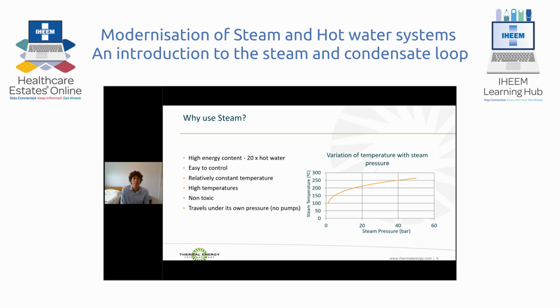So why do we use steam? I guess the key reason is the high energy content. It typically has 20 times more energy per kilogram than hot water. The reason for this is we're not taking the temperature energy out of the steam, we're using the latent energy which is released from the phase change of steam to water. Steam also has a very neat function in that for saturated steam, the temperature is controlled by the pressure. There's a direct relationship, as you can see by this curve.